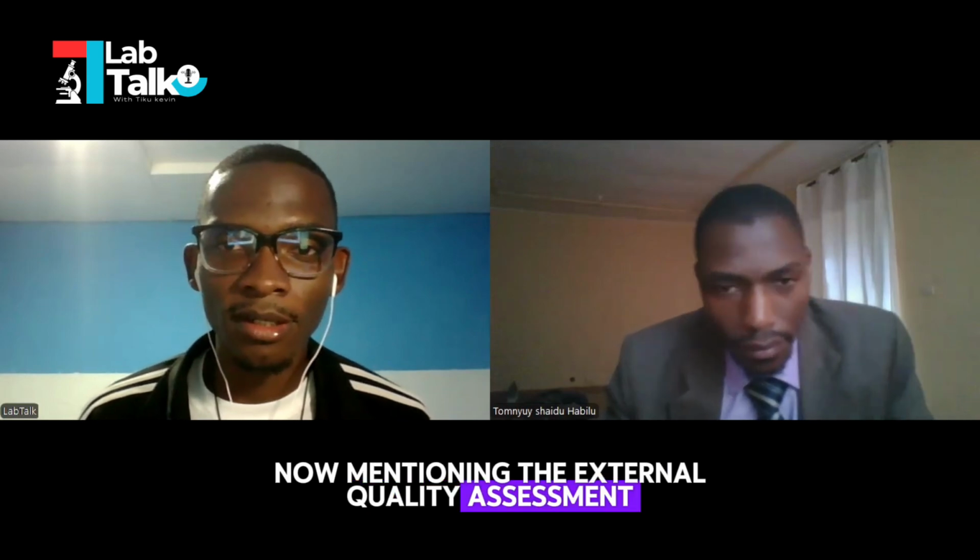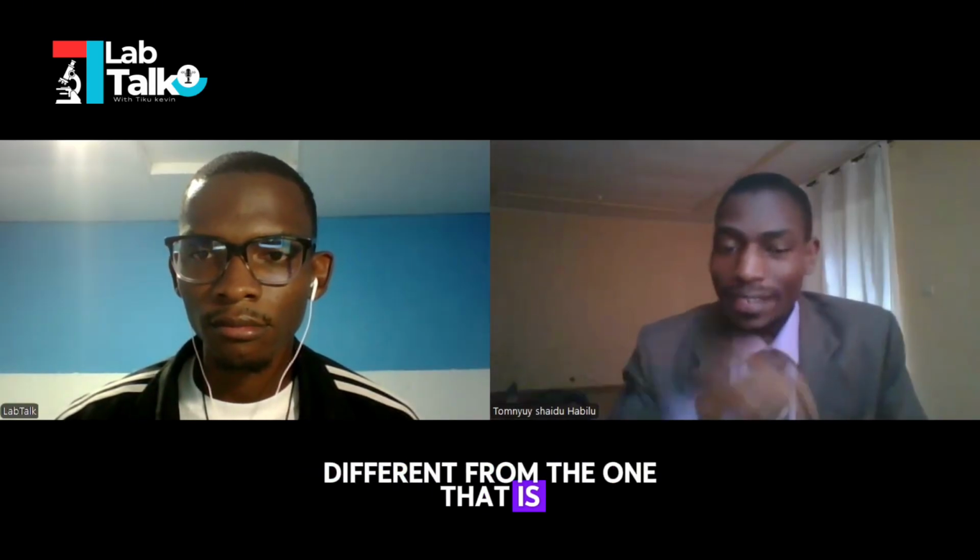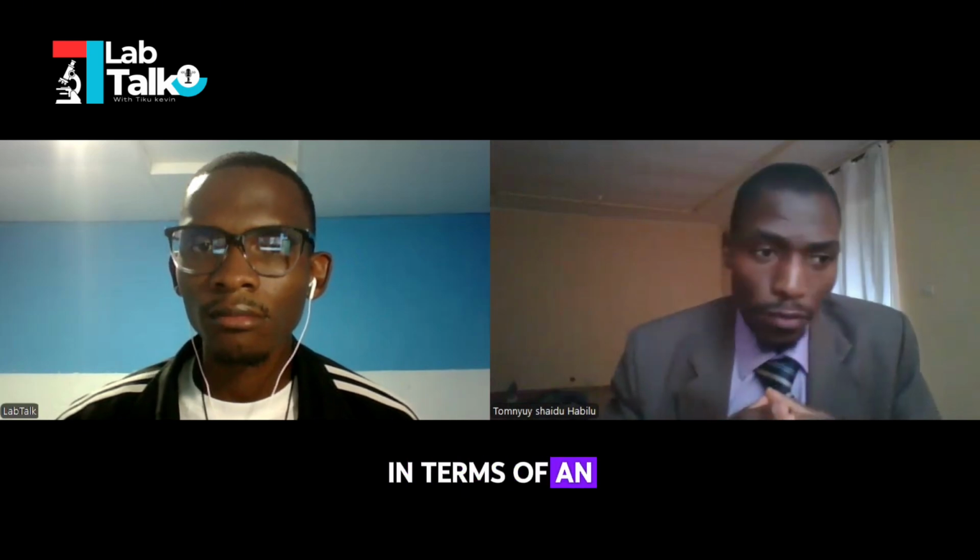Now, mentioning the external quality assessment, what are some challenges that most laboratories face when it comes to implementing quality control in their laboratories? The first challenge, which is the most obvious, is the challenge of supply chain and reagent stability. Because the moment you open a reagent and put it on the onboard shelf, another clock starts ticking, different from the one on the label on the bottle in terms of an expiration date.